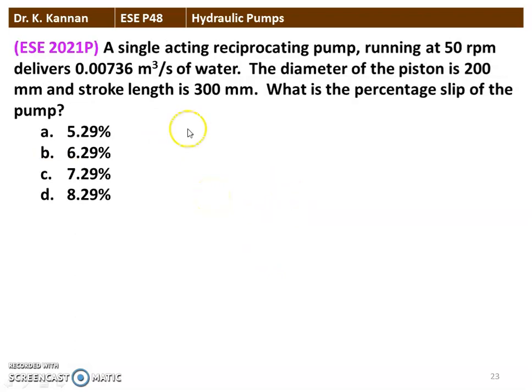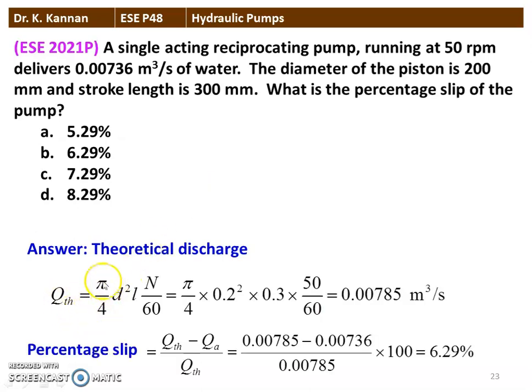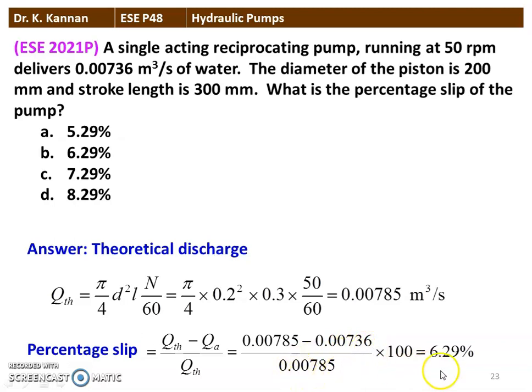The next question from the 2021 question paper: A single acting reciprocating pump running at 50 RPM delivers 0.00736 cubic meters per second of water. The diameter of the piston is 200 millimeter and the stroke length is 300 millimeter. What is the percentage slip of the pump? The theoretical discharge equals (pi/4)·D²·L·N/60 = (pi/4) × 0.2² × 0.3 × 50/60 = 0.00785 cubic meters per second. Percentage slip = (theoretical discharge − actual discharge) / theoretical discharge = (0.00785 − 0.00736) / 0.00785 = 6.29%. The correct answer is option B, 6.29%.